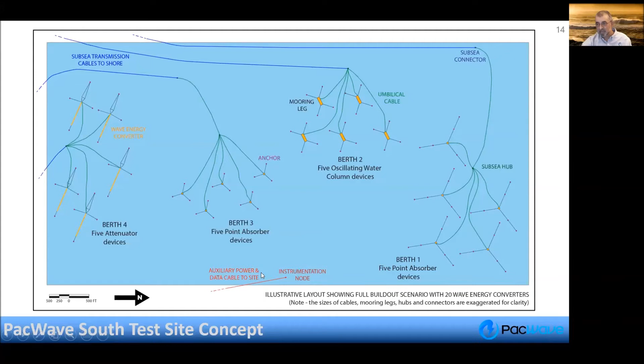The subsea cables themselves are 36 kV, three-conductor AC cables, capable of supporting up to 5 megawatts per cable, giving us 20 megawatts per site.